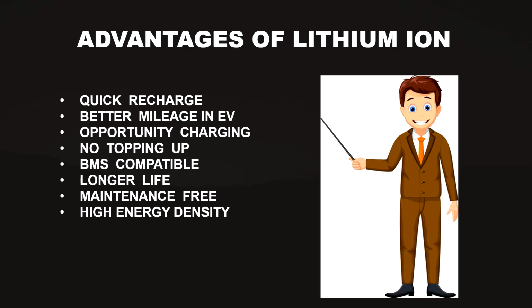The significant advantages of lithium ion are quick recharge, better mileage in EVs, and the possibility of opportunity charging. There is no topping up with distilled water required. Lithium ion batteries are also BMS compatible, where the BMS can indicate the state of charge, overcharge, over discharge, and individual cell voltages. Additionally, the BMS can control specific parameters such as cell balancing and current input, and can also turn off the charger.